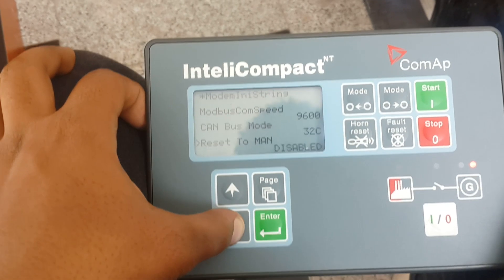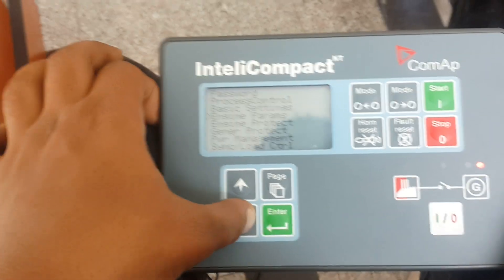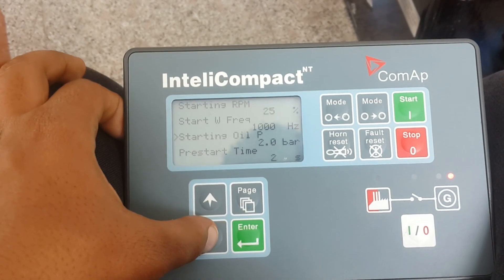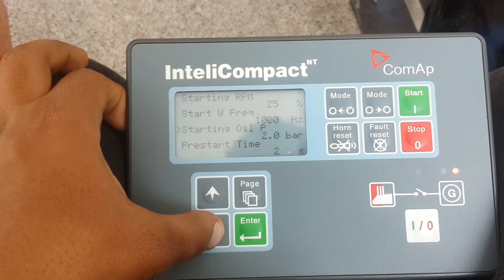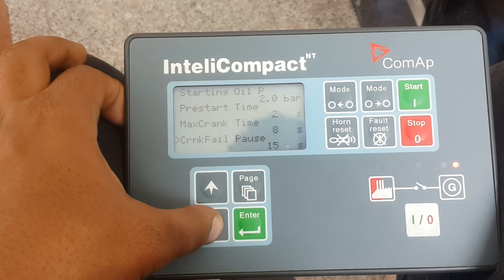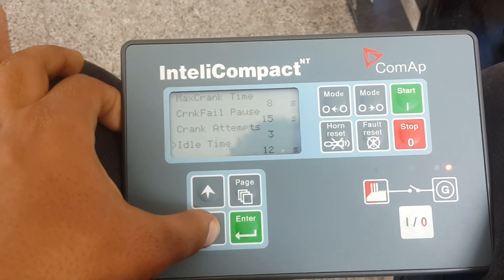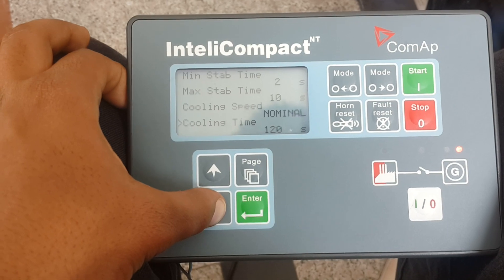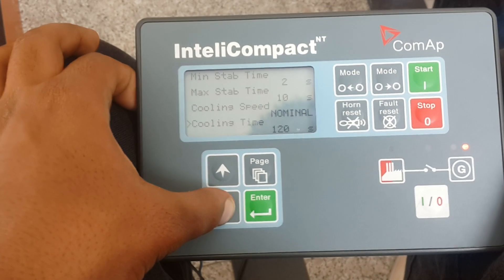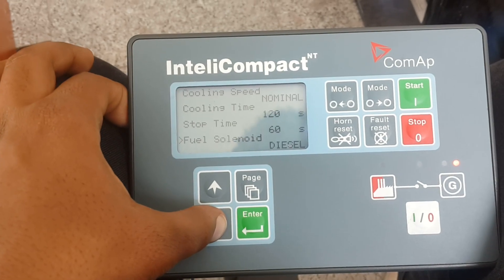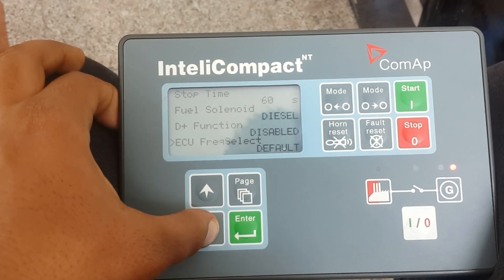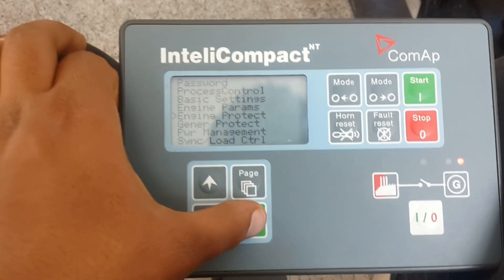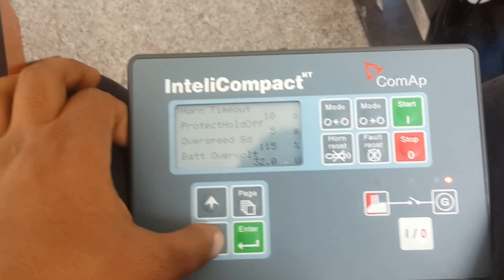In the controller mode specifically — here are the engine settings: starting RPM, starting frequency, oil pressure pre-start time, maximum crank time, crank fail pause, crank attempts, idle time, minimum, max stable time, cooling speed nominal. They didn't adjust the idle speed, so it stays with the nominal. Cooling time, the D+ Function is disabled, frequency selection is default because the gen set we are dealing with here doesn't have an ECM — it's just a conventional type.